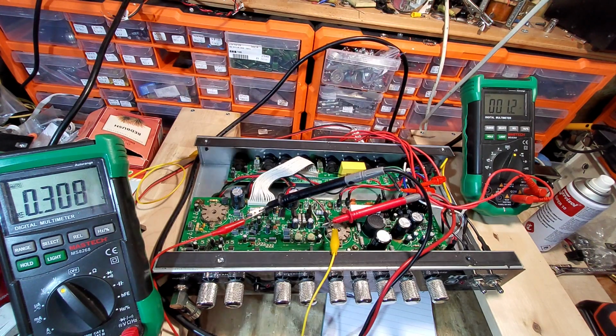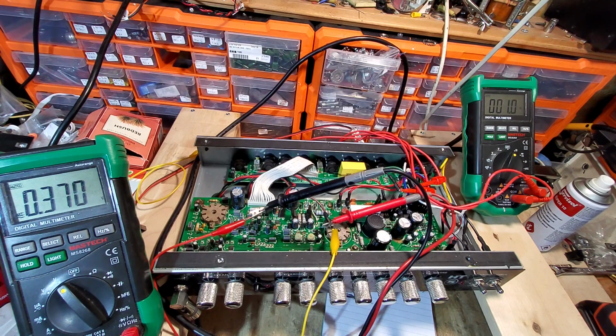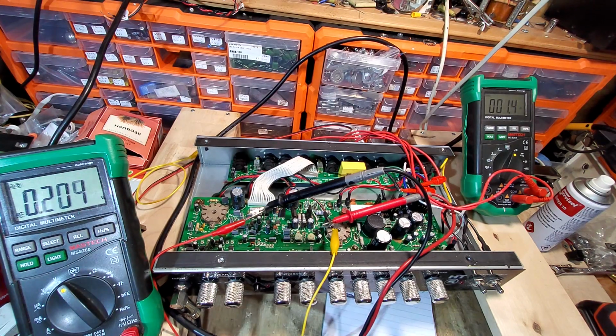Right, we've got this all set up, ready to do this turns ratio test. So we'll only be using a low voltage on this variac. The one thing to remember if you are going to do this, obviously you're going to use a plug top with bare wires, and you need to make sure you put that away as soon as you've done with it, because if you leave it lying around, how many times have you put the wrong plug in? And if you plug that in with bare wires, that won't be very pleasant.